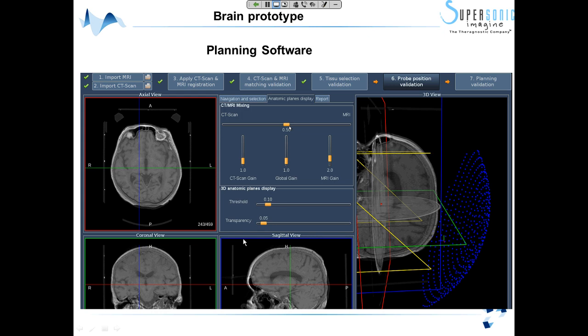So based on the MR images, and you will notice that previously I showed you an image where you could not see the skull. The skull appeared as black, and you can see here details of the skull, because in fact this is a fusion between MR for the brain and CT images for the bone. So we have here combined access to MR for anatomy and CT for aberration correction, so that once the target is selected, here is the red point here at center, based on the anatomical MR image, the software defines the best location of the transducer array in blue over there.